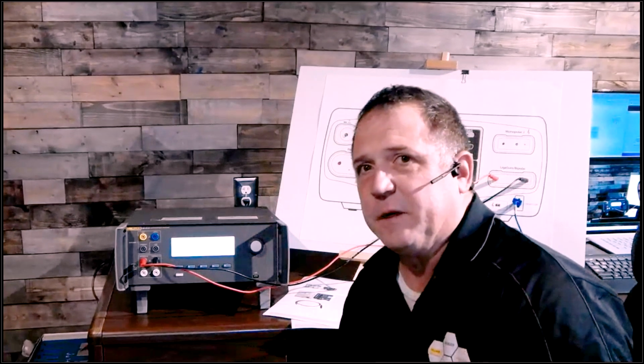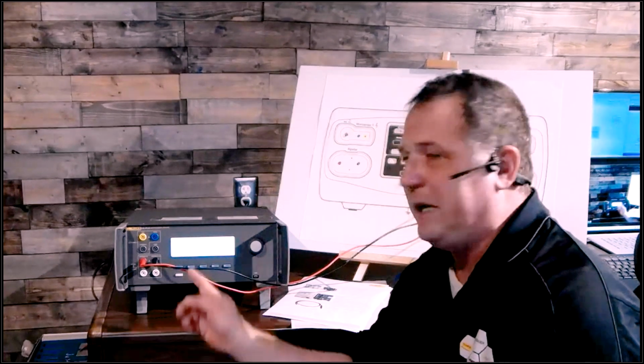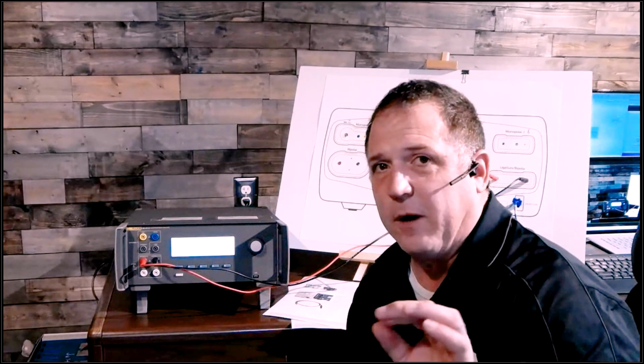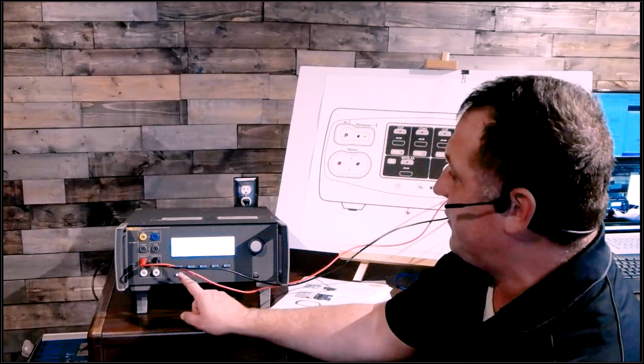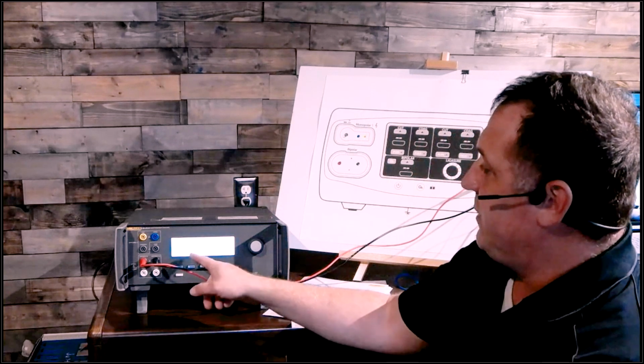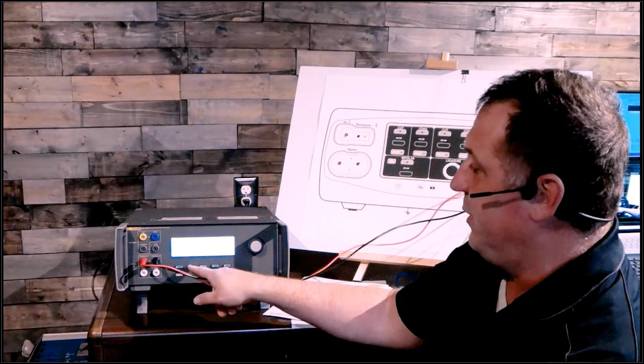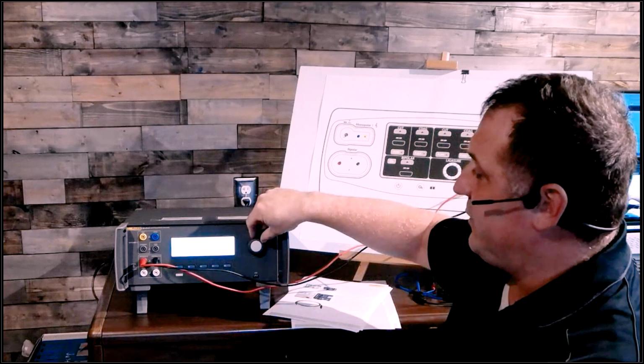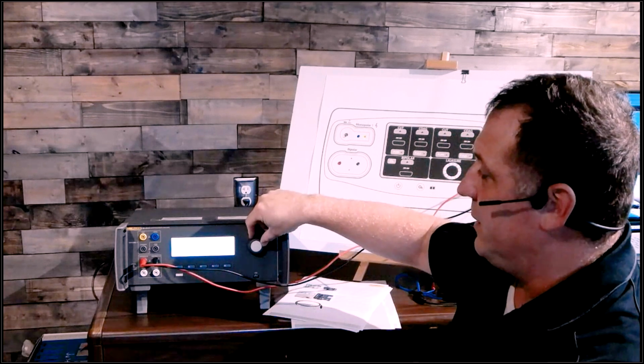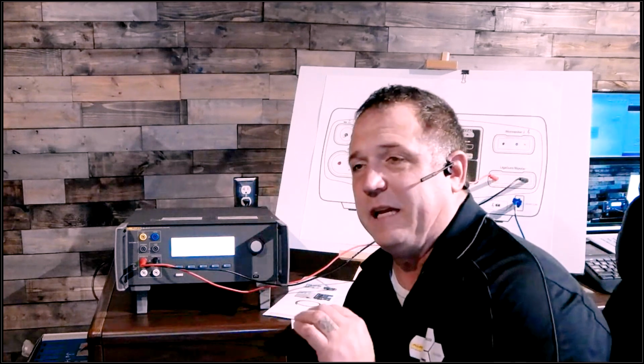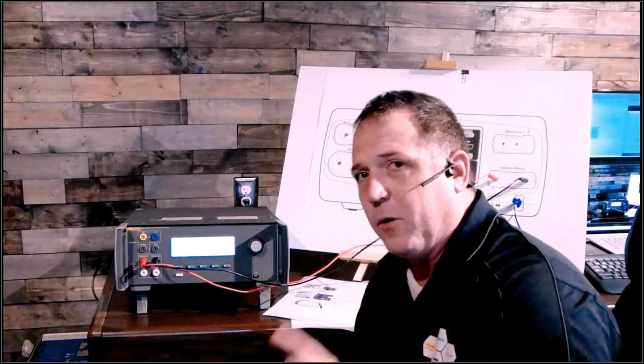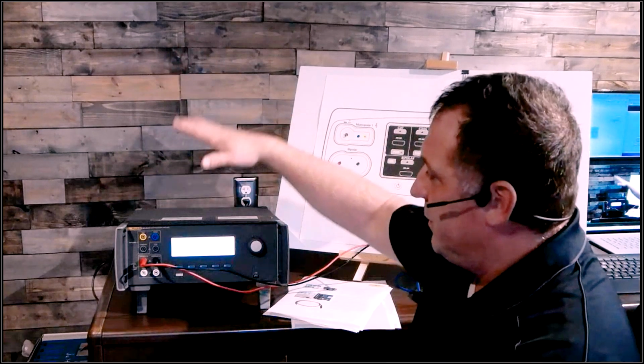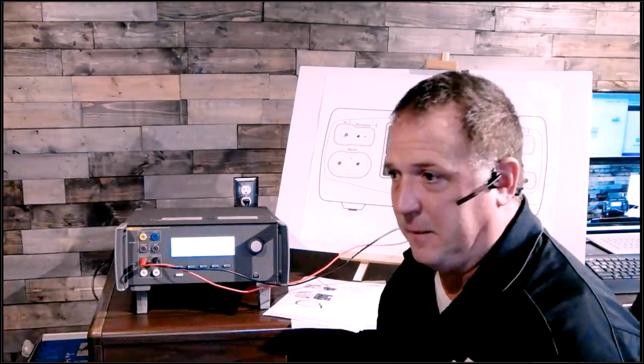But we're changing the frequency of the energy. So while you get a reading here, a better way to get a more accurate result is to back out of this screen and go into the vessel sealing screen, F2. Apply your 200 ohm load. This changes how the ESU reads that energy and gives a more accurate measurement. So change this to vessel sealing here.